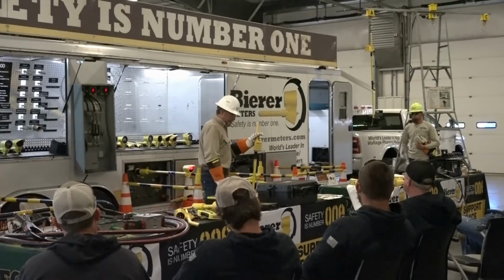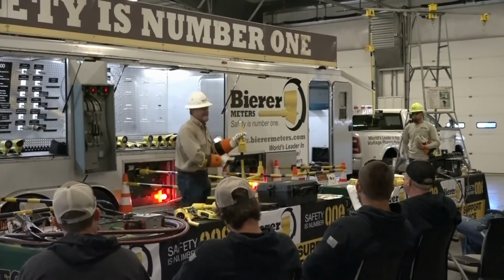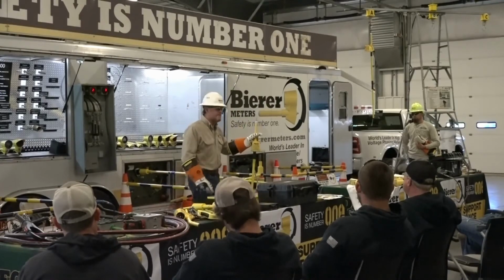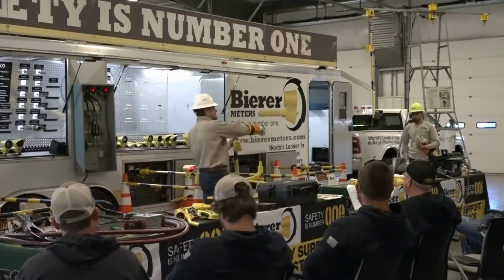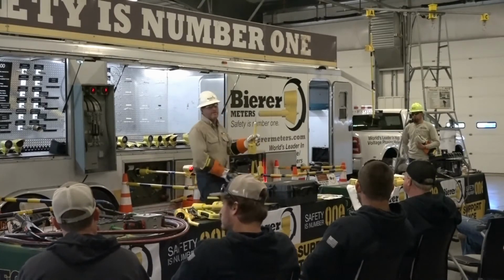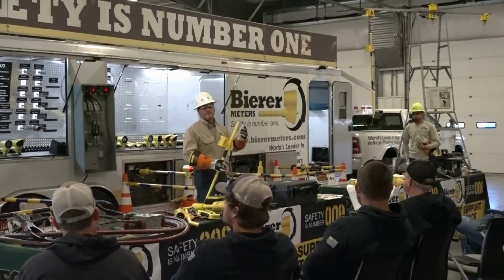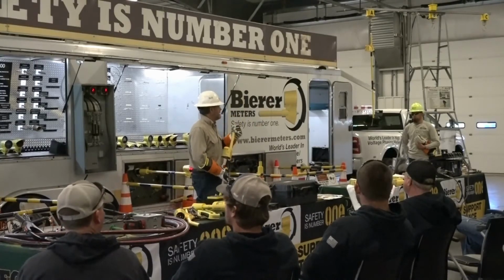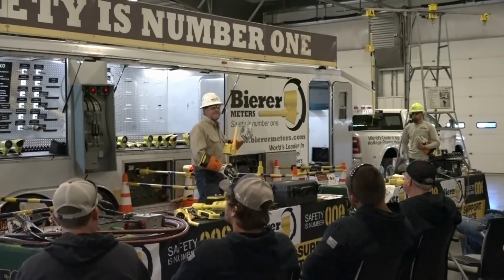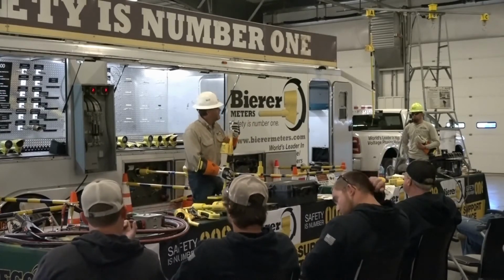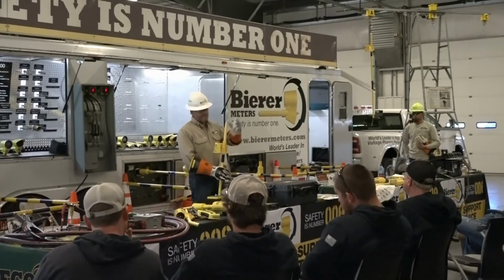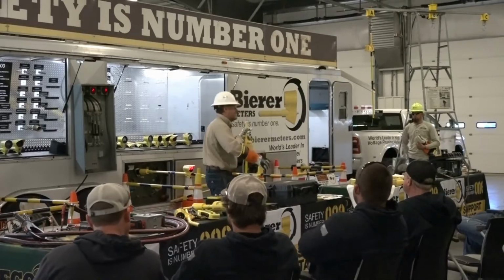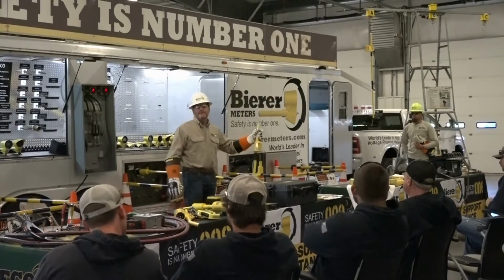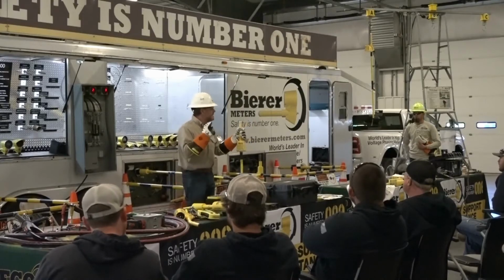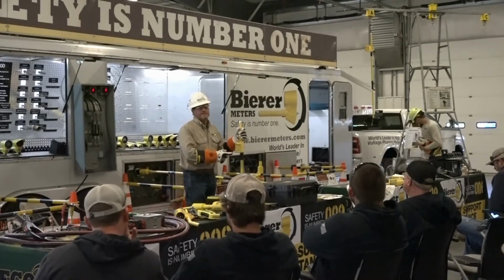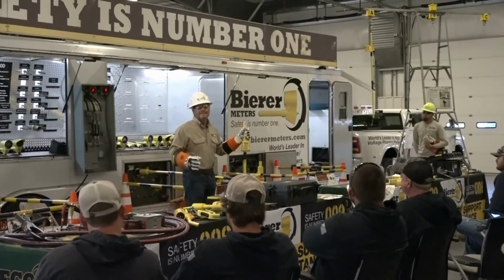You can also identify, because this reads AC and DC voltages, so you can use a 100-volt battery pack, energize a cable with 100 volts, go to the other side, and this picks it up so you can ID with it too. Phase with it obviously, and verify voltage from 1 volt on up to 50 kV, and with some extensions you can go to 150 kV. It's a very, we call it a multimeter. It does more work than any other tool in the industry. Seriously.